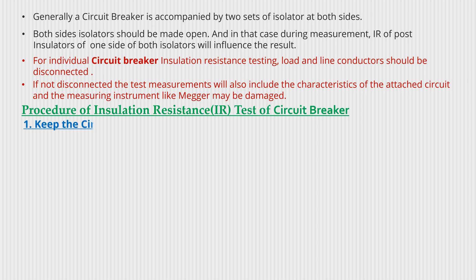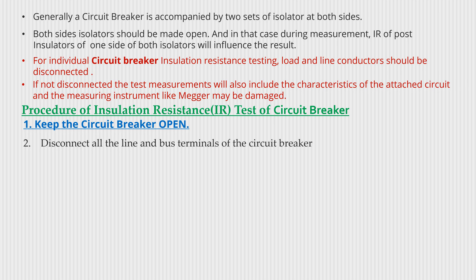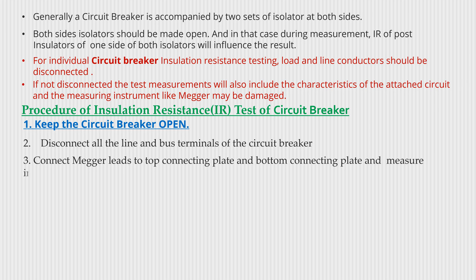Procedure of insulation resistance IR test of a circuit breaker: With the circuit breaker open, disconnect all the line and bus terminals of the circuit breaker. Connect the megger leads to the top connecting plate and bottom connecting plate and measure the insulation resistance IR value in between both plates.